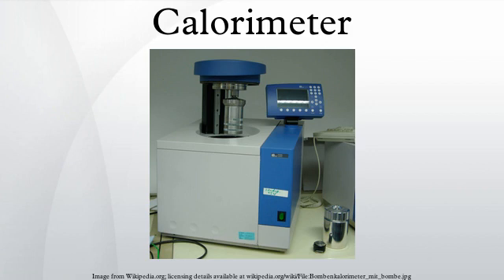A small correction is made to account for the electrical energy input, the burning fuse, and acid production. After the temperature rise has been measured, the excess pressure in the bomb is released. Basically, a bomb calorimeter consists of a small cup to contain the sample, oxygen, a stainless steel bomb, water, a stirrer, a thermometer, the dewar or insulating container, and ignition circuit connected to the bomb.